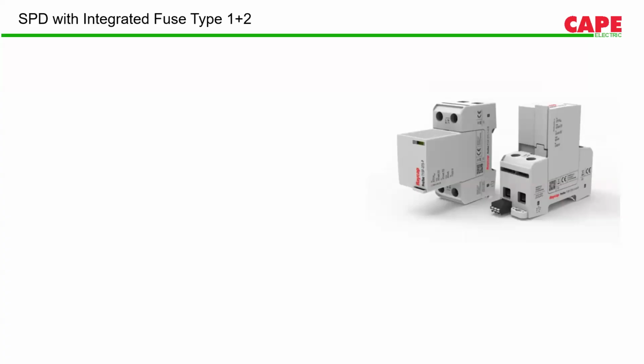Plus, fuses increase the complexity in the circuit. You need to do the wiring. Sometimes the fuses blow, but the SPDs are still working properly. And again, these are parallel connected devices. We have to check physically whether the fuse is working or it has blown. In that case, the SPD gets disconnected because of the blown fuse. Now, to avoid all these confusions and complexity, there is another option.